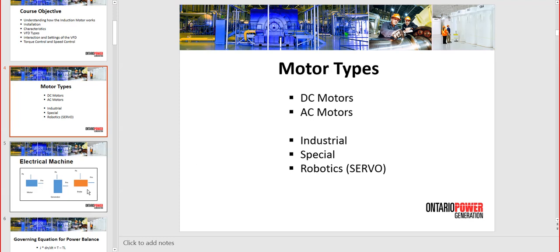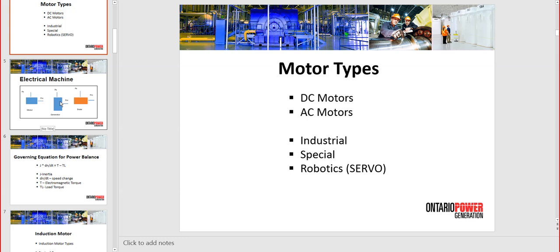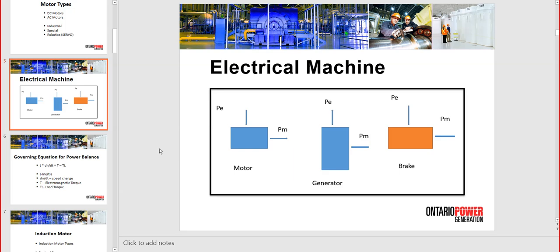In order to start the discussion and to understand the difference between the VFDs and these machine controls that we talked about, including the servo, please remember that the electrical machine is an electromechanical converter, so the same equipment can operate as a motor, a generator, or a brake. When we supply electric power and deliver mechanical power to the shaft, that is a motor. When mechanical power is supplied to the electrical machine and it delivers electrical power, it is a generator. And intentionally I drew the generator this way because a larger diameter will help a generator maintain the speed and maintain the 60 Hertz.